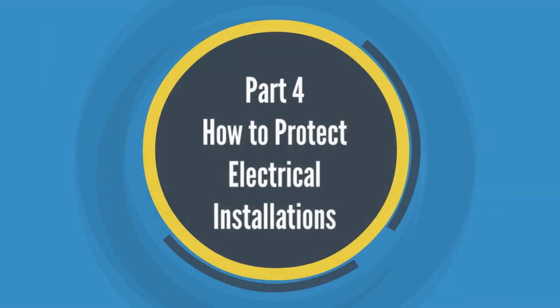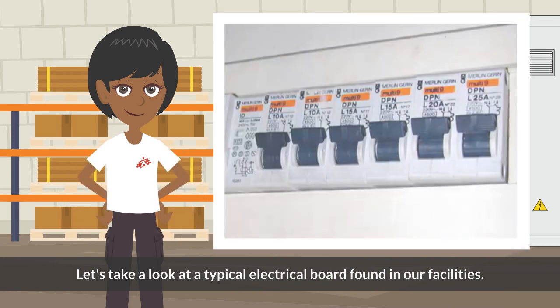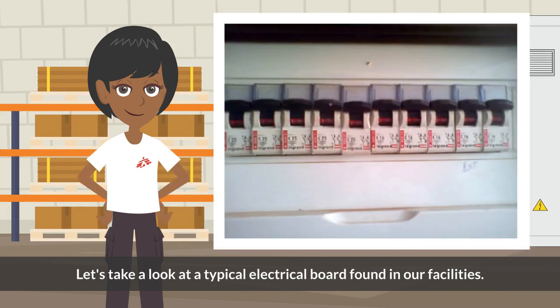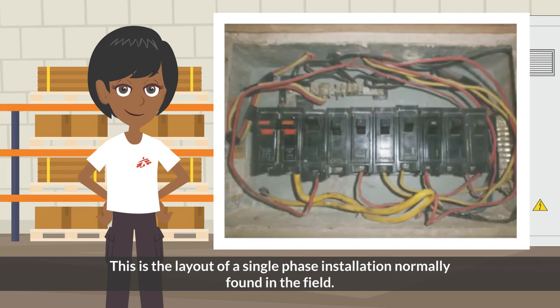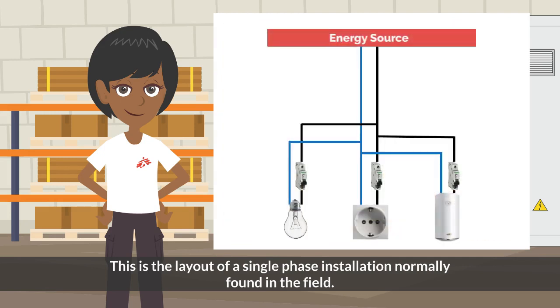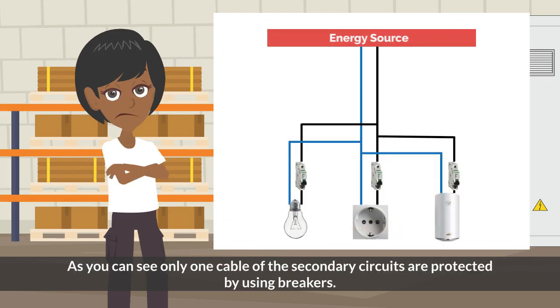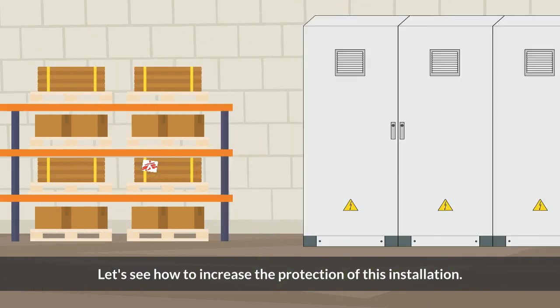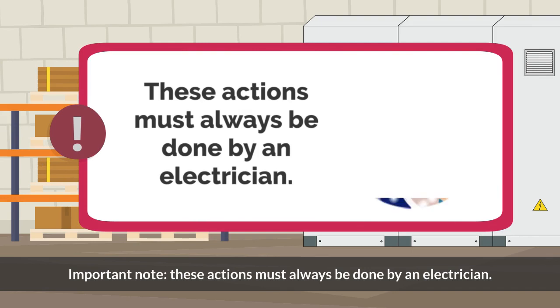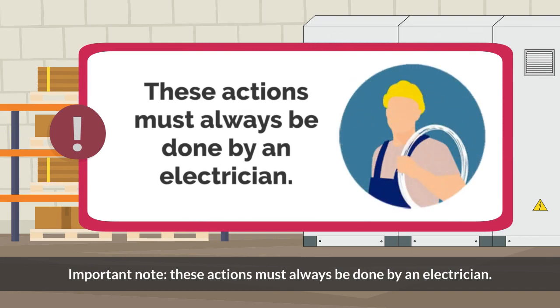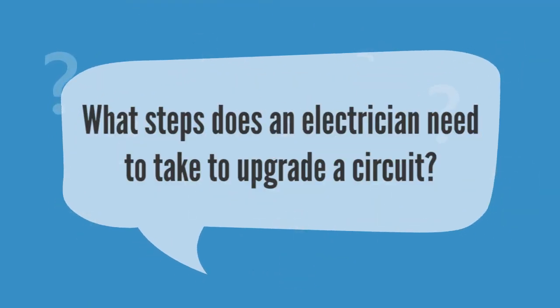Part 4. How to protect electrical installations. Let's take a look at a typical electrical board found in our facilities. This is the layout of a single-phase installation normally found in the field. As you can see, only 1 cable of the secondary circuits is protected by using breakers. Let's see how to increase the protection of this installation. Important note: these actions must always be done by an electrician. What steps does an electrician need to take to upgrade a circuit?